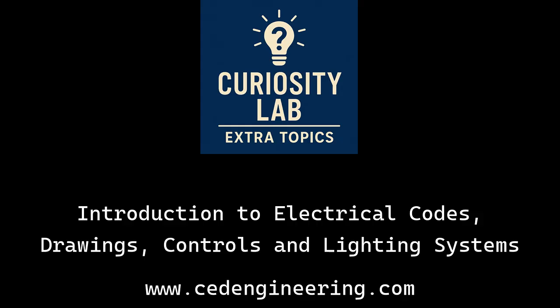Globally, you have the IEC, International Electrotechnical Commission, setting standards, and one really important IEC standard defines IP ratings, ingress protection. That IP code, like IP67, tells you how well an enclosure protects against solids, like dust, the first digit, and liquids, water, the second digit. It's crucial for matching equipment to the environment.